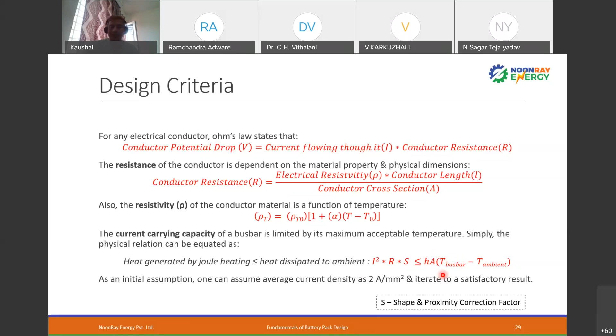An example here: a bus bar should be designed for a maximum resistance of 10 to the power minus 4 ohm. The length of the bus bar is constant at 6 cm. Assuming the bus bar can go up to a temperature of 50 degrees centigrade, find the cross section of the bus bar. Material property is copper; we have selected copper. So first you need to find resistivity at 50 degrees centigrade. Then resistance of the copper bus bar R is already given. This is our design criteria.